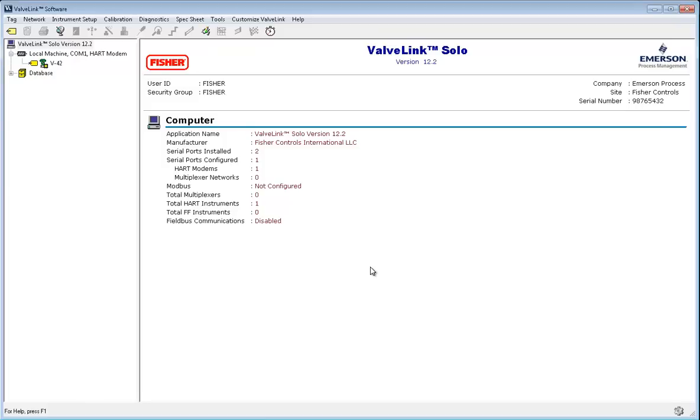There's the performance tuner, stabilize and optimize, and manual tuning. We will be going over each of these tools today. These tests do cause your valve to stroke, so make sure it is isolated from any processes before running.